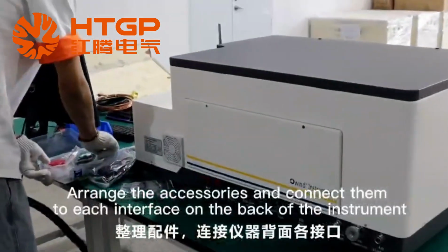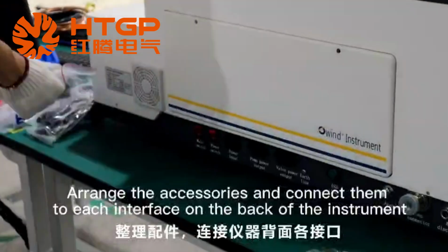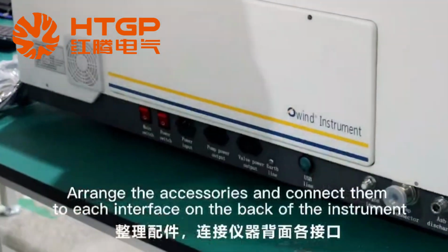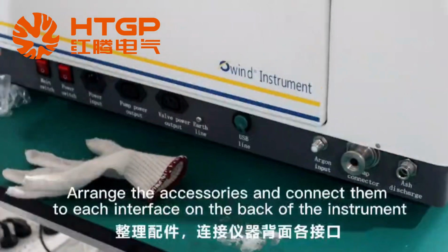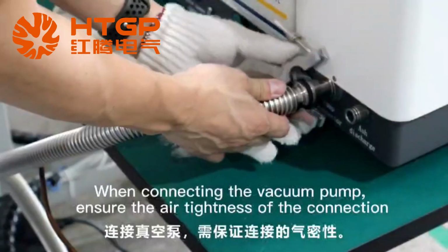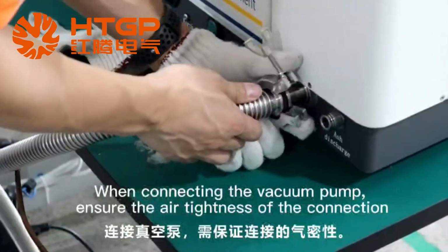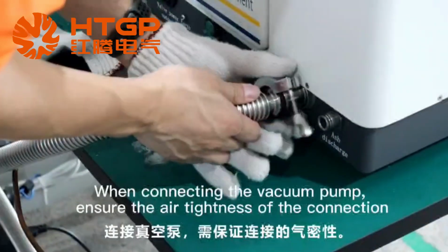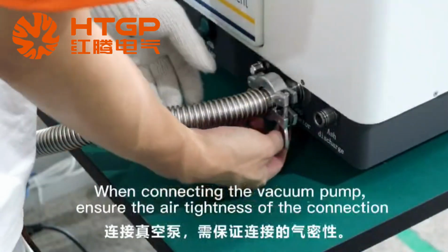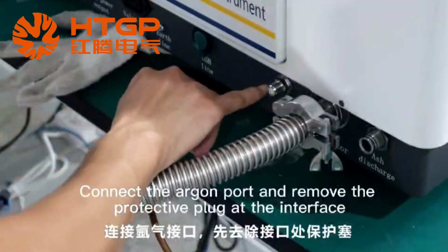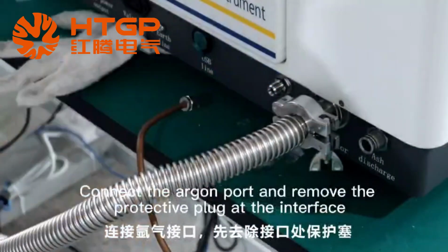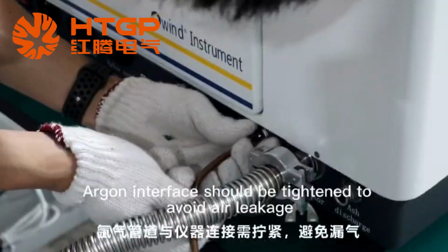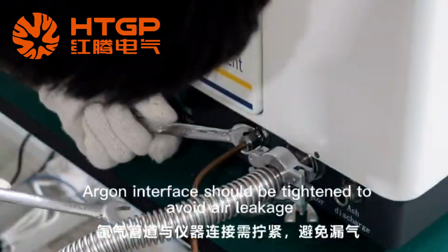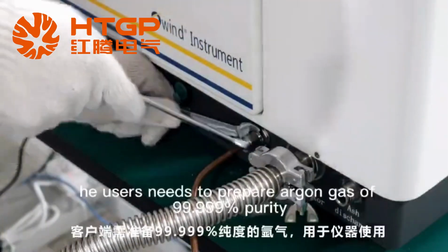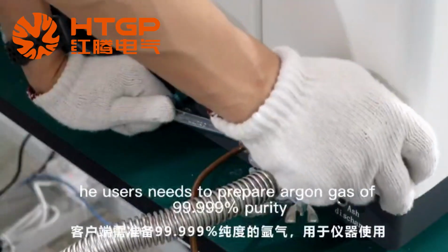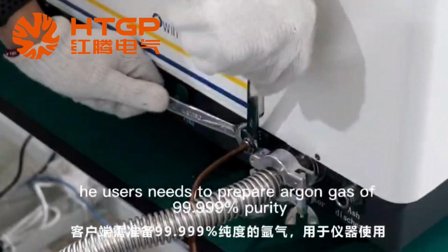Arrange the accessories and connect them to each interface on the back of the instrument. When connecting the vacuum pump, ensure the air tightness of the connection. Connect the argon port and remove the protective plug at the interface. Argon interface should be tightened to avoid air leakage. The users need to prepare argon gas of 99.999% purity.